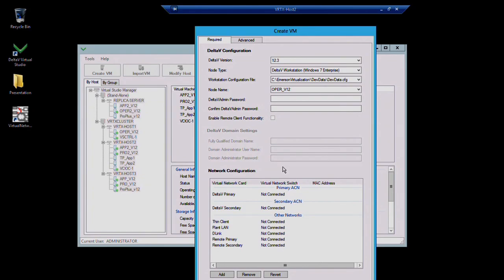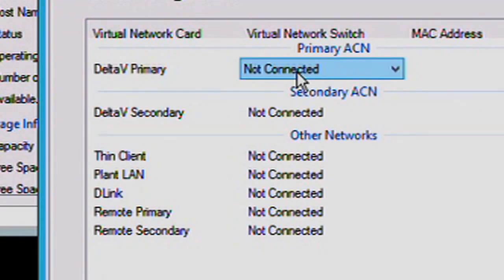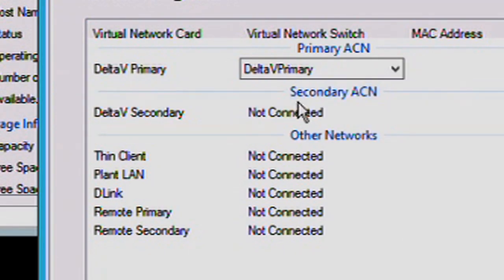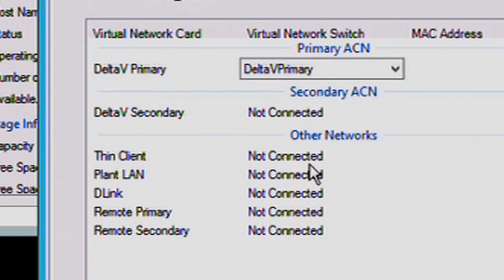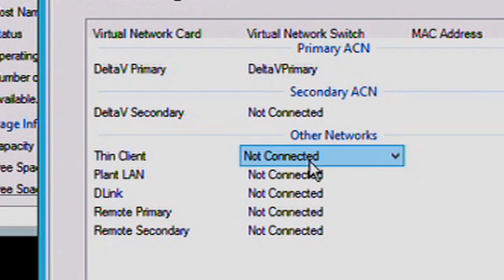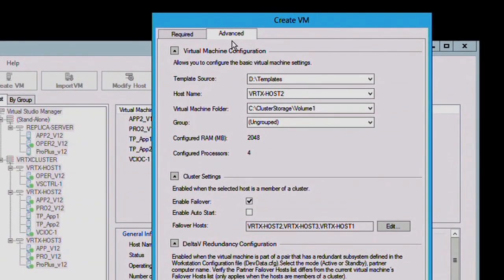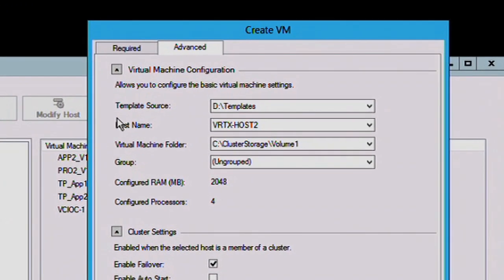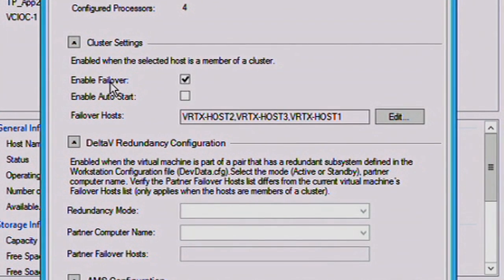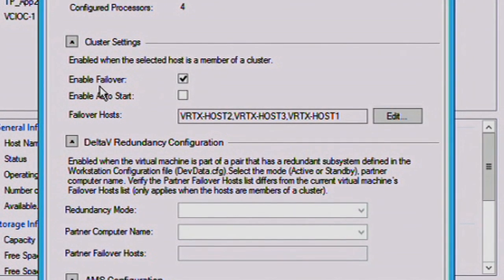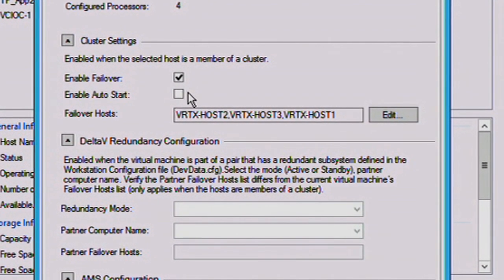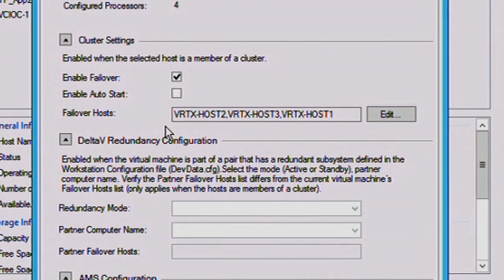You would select what node name you want and then fill out the Delta V admin password information. The only thing remaining is to establish your network connections, which we defined on our host computer. So, it's very easy to just drop down menu and connect. If you're interested in advanced features, you can also come in and specify the amount of memory available, the number of processors. If you're in a high availability environment, you can enable failover and auto restart and specify what your backup failover machines are. And we'll talk about that in another video on high availability and disaster recovery.